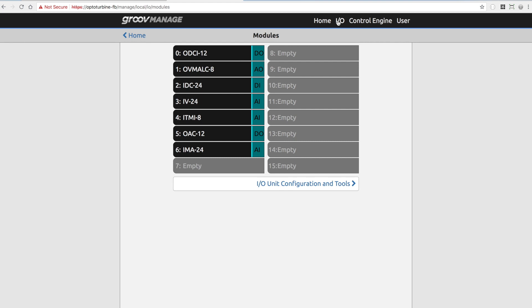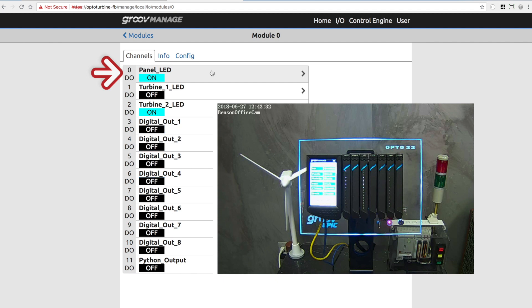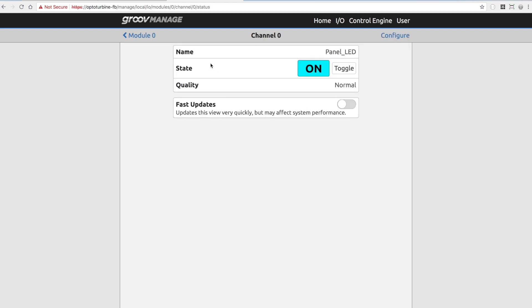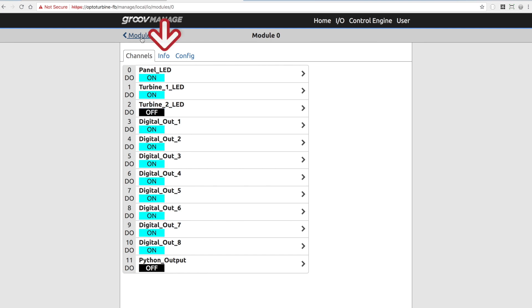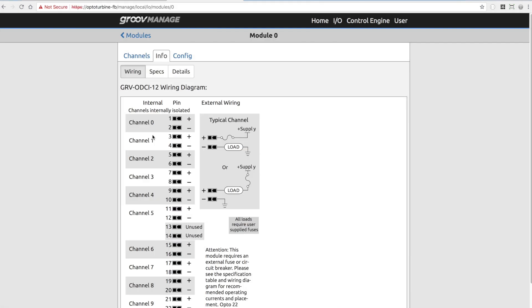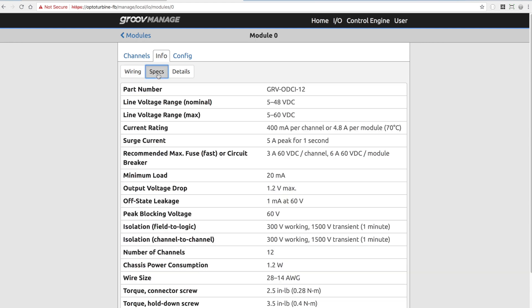Now let's take a look at the I/O. I've already wired up all the I/O, so now I just want to troubleshoot and make sure everything is working properly. I notice that all my I/O is automatically configured on the device. I'll click on a digital output — channel zero is my panel LED. I can force the I/O point on or off and check to make sure it's working properly. And indeed it is. If it didn't work, the first thing I'd want to check is the wiring. I can simply click on the Info tab, and there's my entire wiring diagram to confirm the panel LED is wired up properly, along with all the specs to make sure whatever I'm driving meets the module's specs.